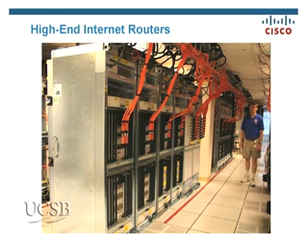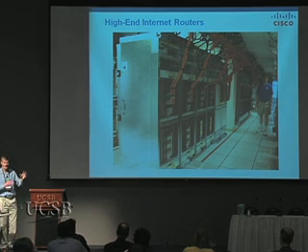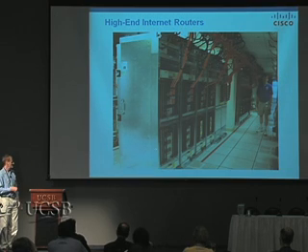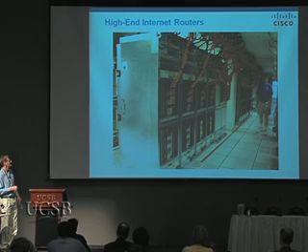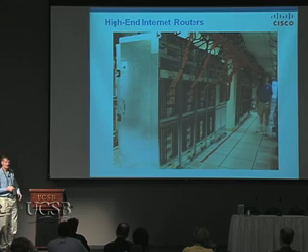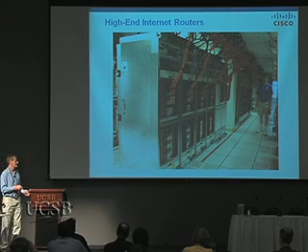That's the class of equipment in the internet core today — AT&T, Verizon, Sprint all have this. Each rack is potentially 13 kilowatts at maximum, though usually not at maximum. This presents a facilities challenge much like what data center engineers face — racks of equipment needing cooling and power management.